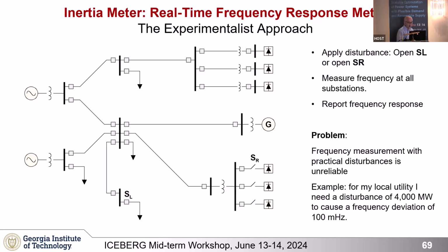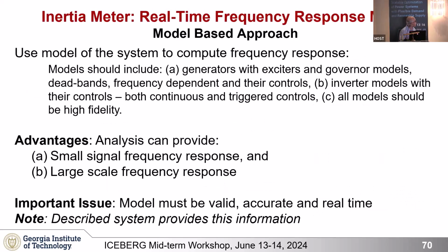So here is the alternative approach. I have this system, the digital substation, where I have validated models. Why can't I use the validated models to tell you the frequency response and the inertia of the system? For this, I need appropriate, validated models that represent what will happen with the frequency change, including the AGC controllers and all of this.